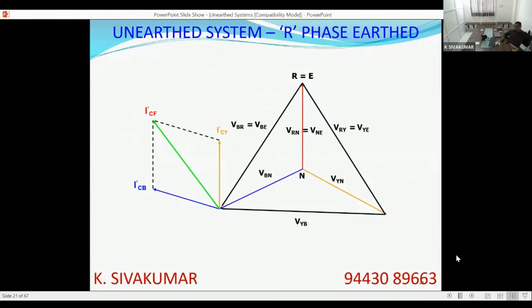Since the phase voltage has become line voltage, the current also will be leading the phase voltage by 90 degrees. That is, ICY and ICB. ICY will be leading VYE by 90 degrees, and ICB will be leading VBE by 90 degrees. The total net current flow during this fault, the capacitive discharge current, is the fault current. It is the vector sum of ICY and ICB.